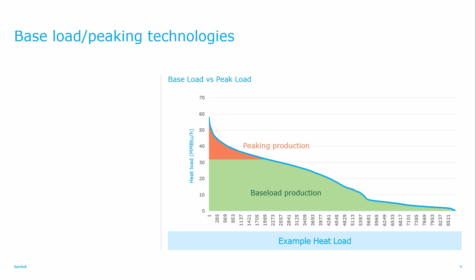What we're trying to do is design our base load around higher capital expenditures, so you're utilizing that asset. It's going to be a cheaper fuel, so we'll show that in a couple of slides, but utilizing more electric-based equipment for that base load production. When you size that base load for about 55% of your peak, you are covering typically around 90% of your annual load. That's a bit of an optimizing sequence that needs to go on in order to figure out the optimal sizing.